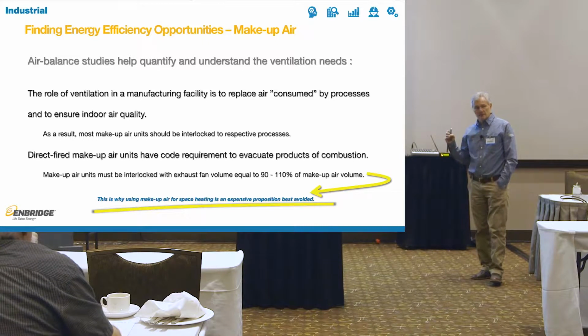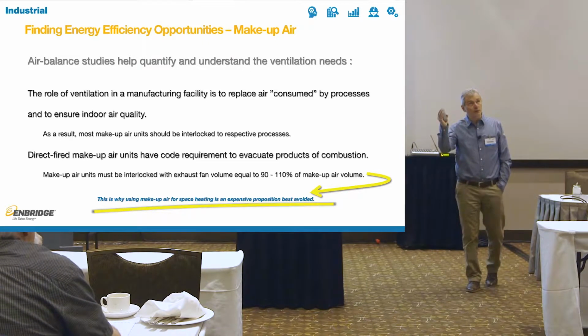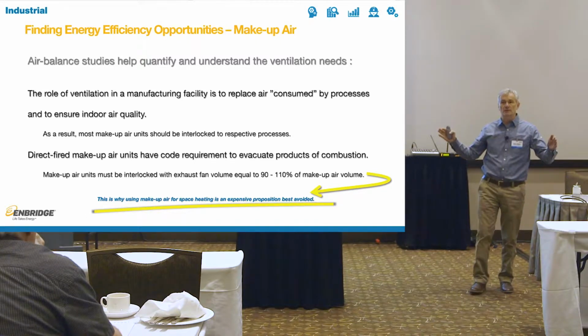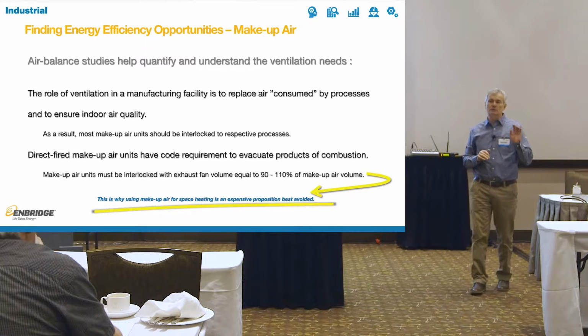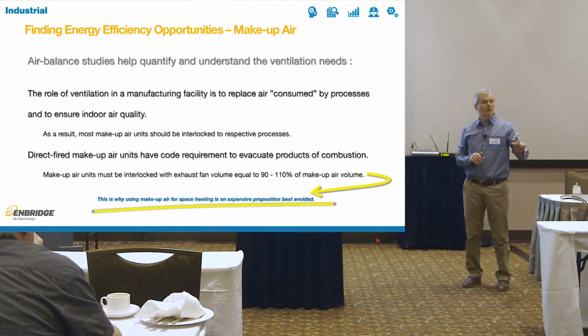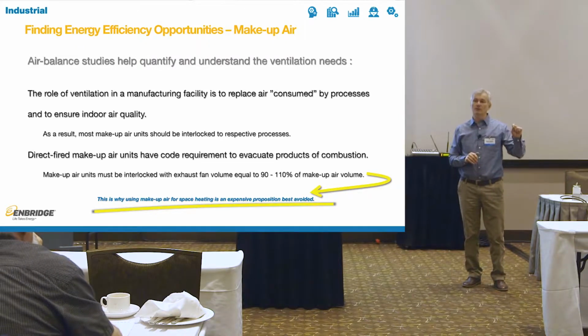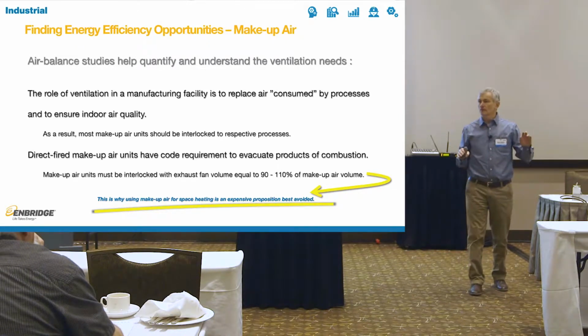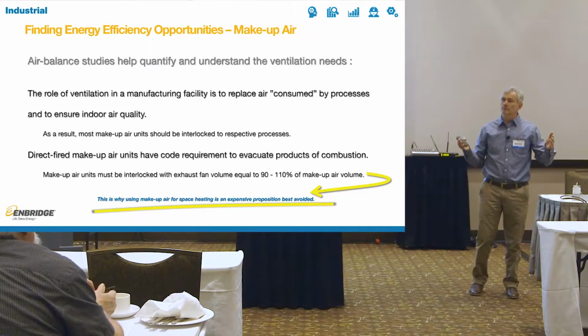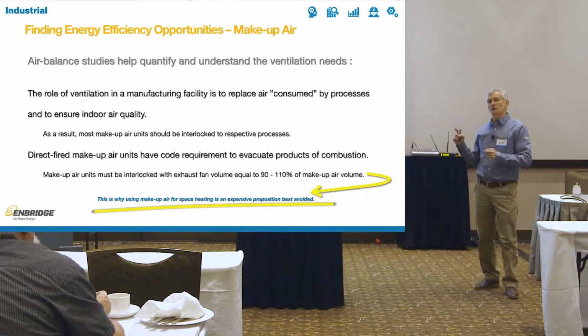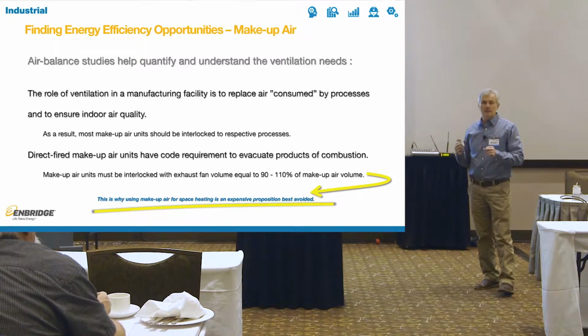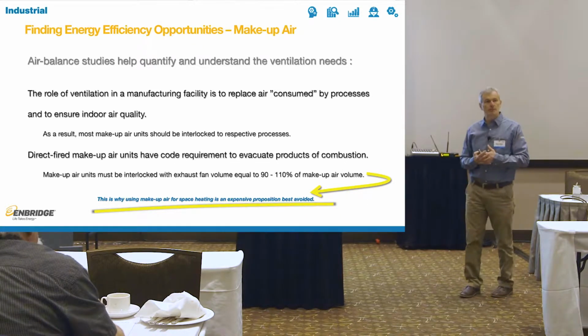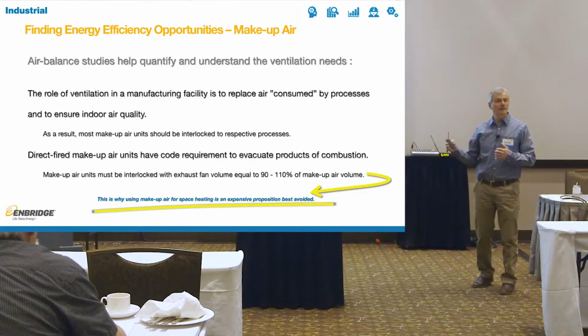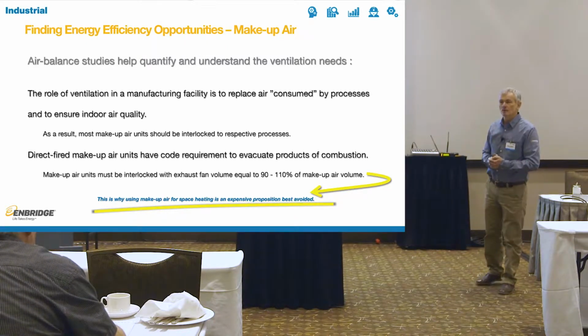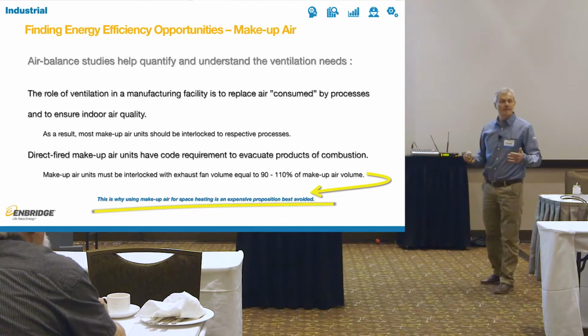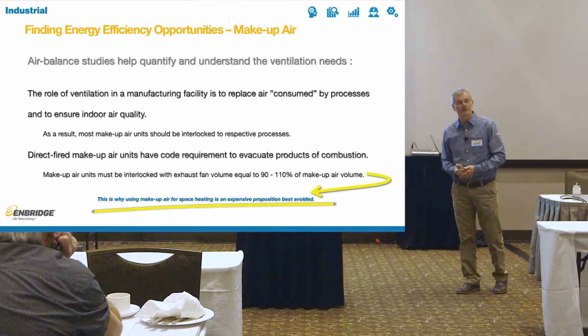To start with, as a basic principle, if you're in this room, for example, like this one here, and if this was your manufacturing space, all the makeup air, all the fresh air that you would have to supply is about 20 cubic feet per minute per attendee. So for each one of us, 20 cubic feet per minute, that's all you have to supply. So 20 people times 20, 400 CFMs. 400 CFM is all you would have to supply here. Have you ever seen a 400 CFM makeup air unit anywhere in your facility? Probably not. You probably have to add 2 or 3 zeros at the back, right? So that makes you wonder why. If it's good for this, why is it not good for the facility?